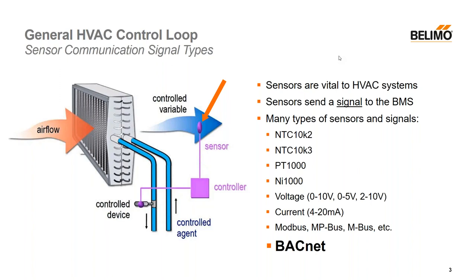The sensor is measuring the temperature of the air coming through the coil. The sensor itself then sends a signal to the local controller, and the controller then takes action based on how it's programmed. The signal sent from the sensor to the controller can come in many different variants. Generally speaking, there are numerous passive temperature signals such as NTC 10K2, 10K3, PT1000, Nickel 1000, and so on. There are also analog signals available in the form of voltage and current — could be zero to 10 volts, zero to five volts, two to 10 volts for modulation.